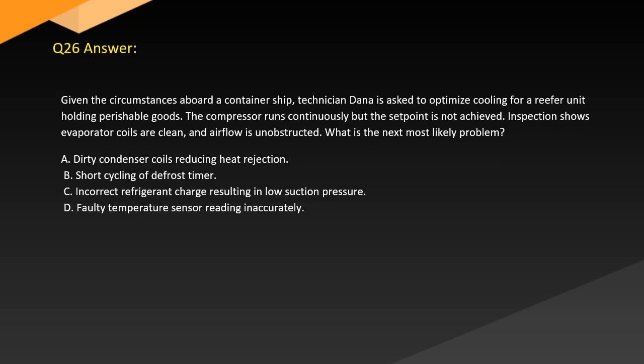Answer. Given the circumstances aboard a container ship, technician Dana is asked to optimize cooling for a reefer unit holding perishable goods. The compressor runs continuously, but the set point is not achieved. Inspection shows evaporator coils are clean and airflow is unobstructed. What is the next most likely problem? A. Dirty condenser coils reducing heat rejection. B. Short cycling of defrost timer. C. Incorrect refrigerant charge resulting in low suction pressure. D. Faulty temperature sensor reading inaccurately.